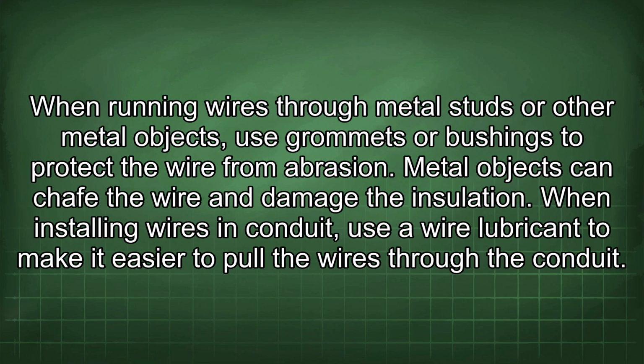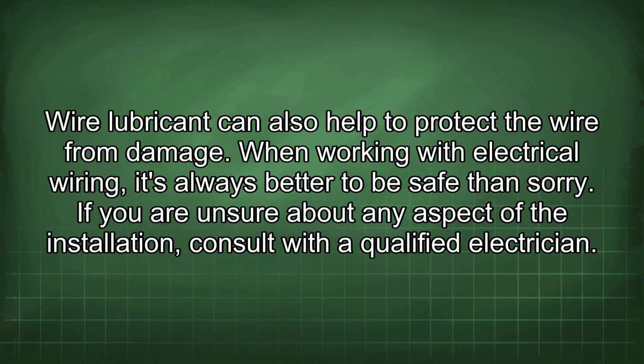When running wires through metal studs or other metal objects, use grommets or bushings to protect the wire from abrasion. Metal objects can chafe the wire and damage the insulation. When installing wires in conduit, use a wire lubricant to make it easier to pull the wire through the conduit. Wire lubricant can also help to protect the wire from damage.